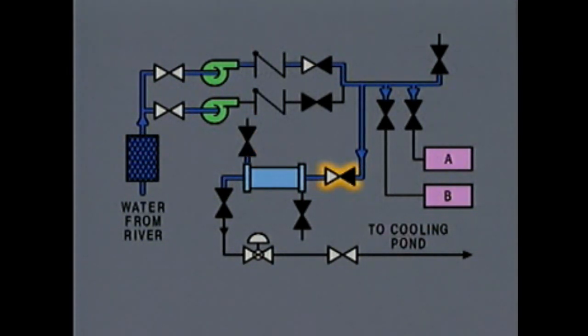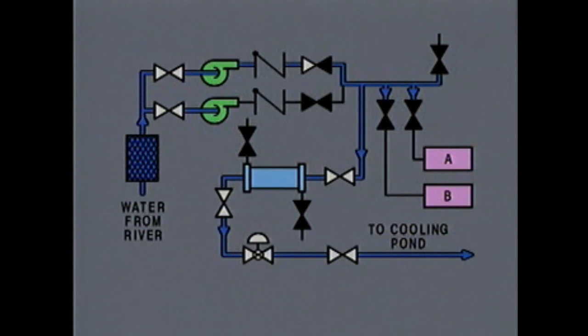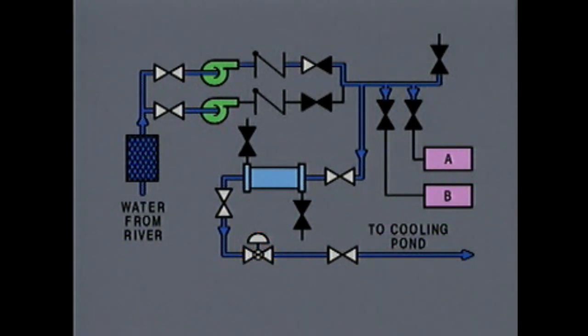The inlet isolation valve is opened completely and the outlet isolation valve is opened. Then this isolation valve is checked to make sure it's open. Water then leaves the lube oil cooler and passes through a pneumatically operated globe valve that regulates the flow of water through the lube oil cooler. The flow has now been established through the lube oil cooler, and the discharge valve at the pump can be opened completely.